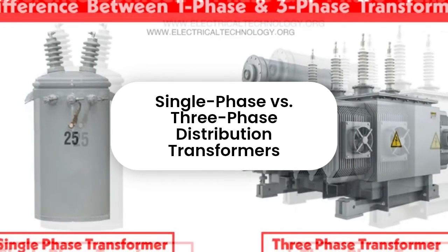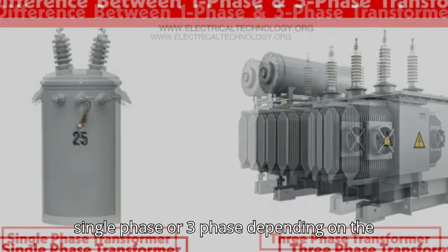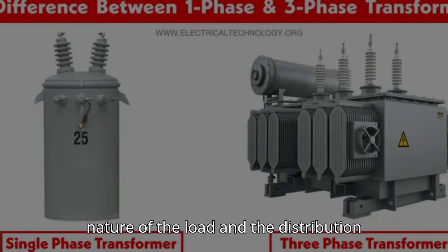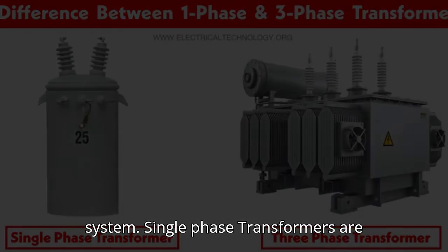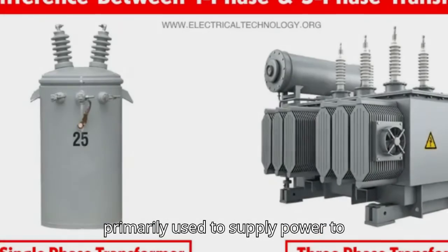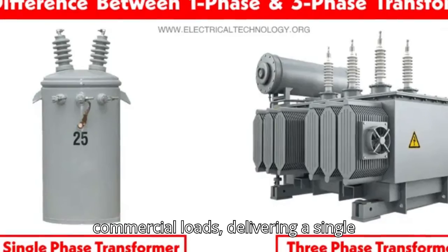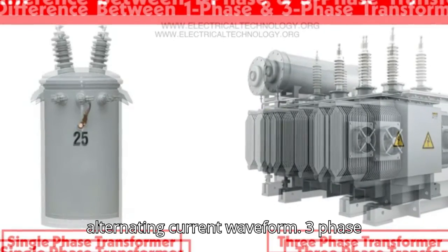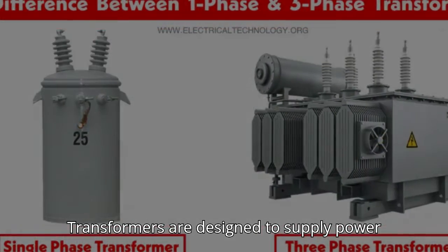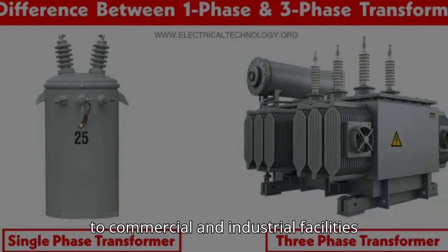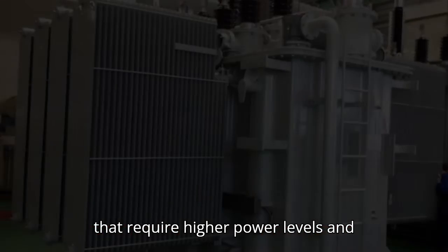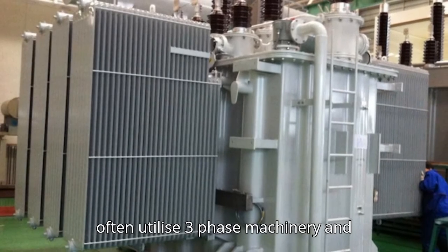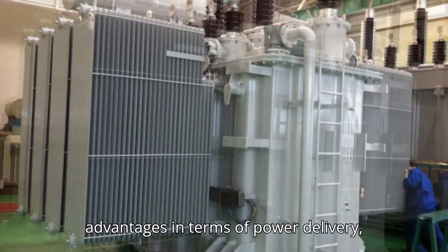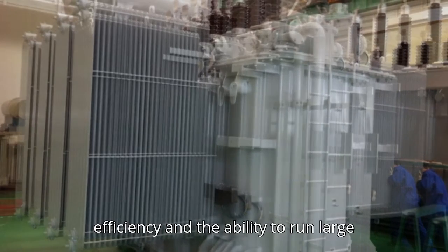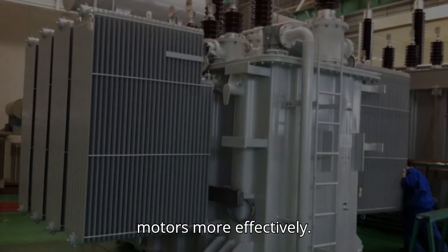Single-phase versus three-phase distribution transformers. Distribution transformers can be either single-phase or three-phase, depending on the nature of the load and the distribution system. Single-phase transformers are primarily used to supply power to residential customers and small commercial loads, delivering a single alternating current waveform. Three-phase transformers are designed to supply power to commercial and industrial facilities that require higher power levels and often utilize three-phase machinery and equipment. Three-phase systems offer advantages in terms of power delivery efficiency and the ability to run large motors more effectively.